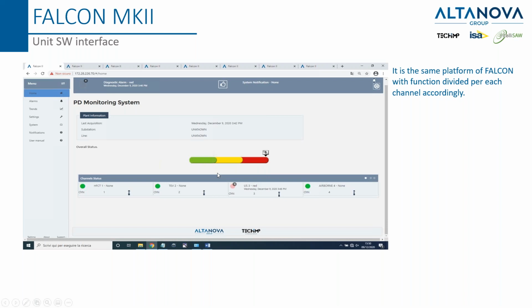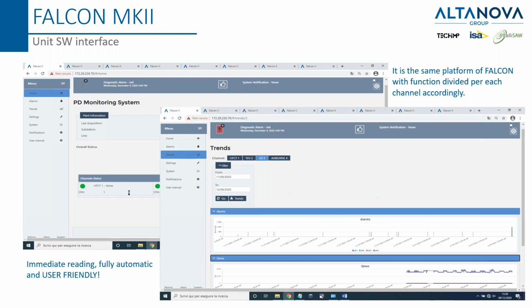That means you can see here you have the status, in this particular case the screen for the HFCT or TEV, and then ultrasonic, which is for the contact type or for the airborne type. If you go to this particular channel, you will have a dedicated page with the trending and information about the state. The principle and the function are exactly the same for the Falcon Mark II as for the Falcon Mark I, but in this case there are 4 more channels.